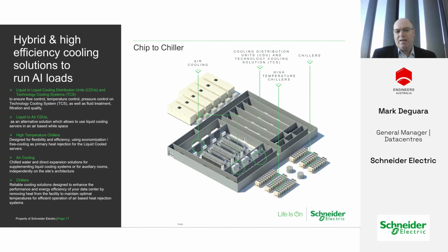There's liquid to air, there's high temperature chillers. What we've seen over the last 5 to 10 years is a real increase in the temperatures coming off the compute. Therefore, if we can drive temperatures up into the chilled water, that means we can have a lot more free cooling. If we're running a 20 to 30 degree chiller, or even 25 to 35, it fundamentally gives us more hours of free cooling. The real challenge we're starting to see with liquid cooling of the chips is we're starting to hit the thermal limitations of the temperature, or the junction point, on these chips.